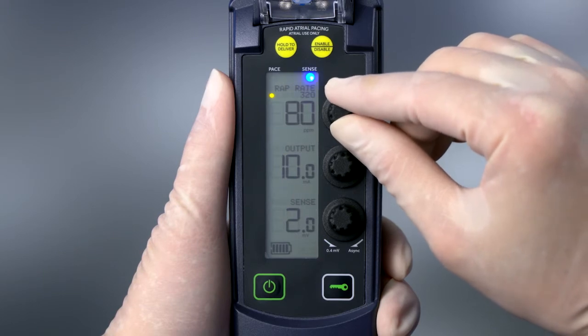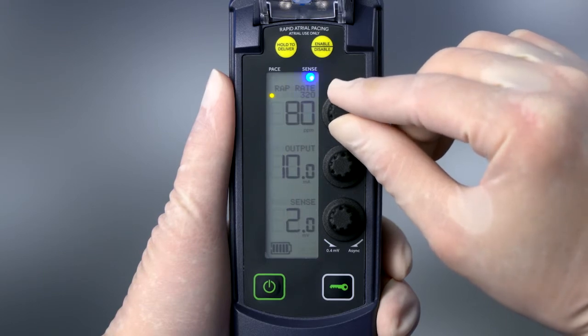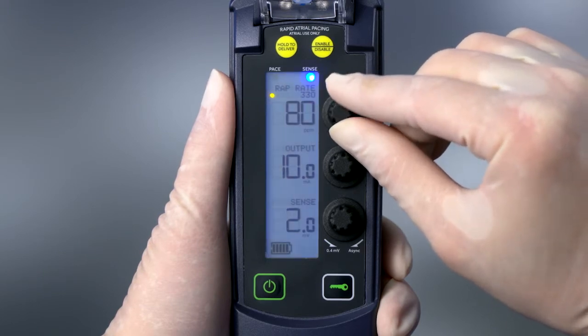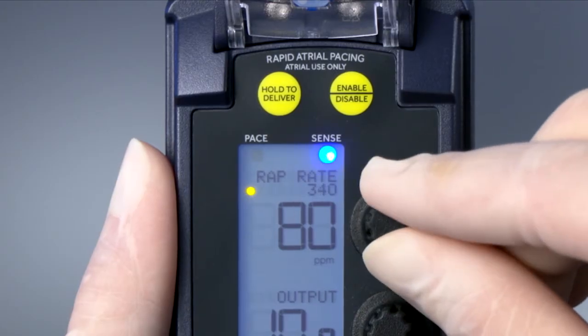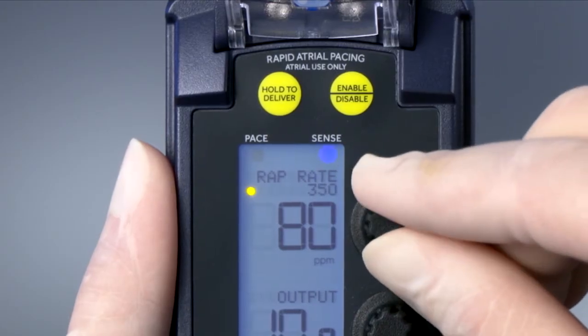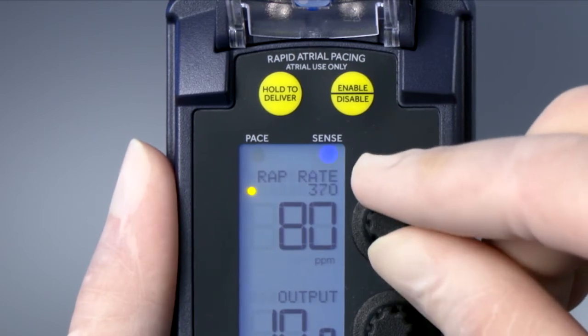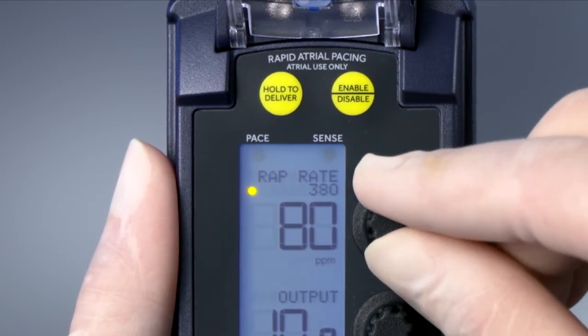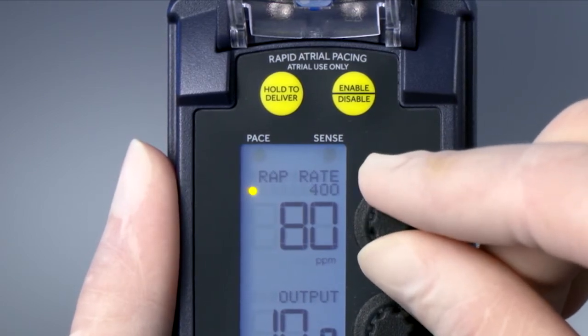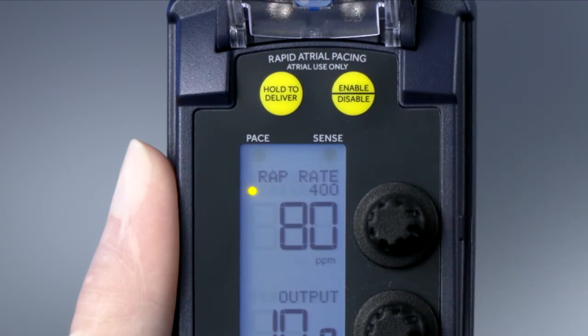Once Rapid Atrial Pacing is enabled, rotate the RAP dial to the desired rate. In this example, the physician wishes to pace the atrium at 400 paces per minute in an attempt to terminate the underlying atrial tachyarrhythmia.